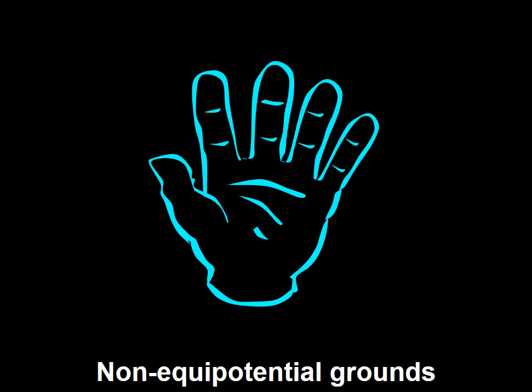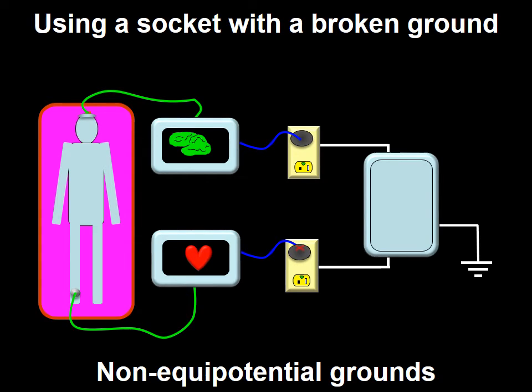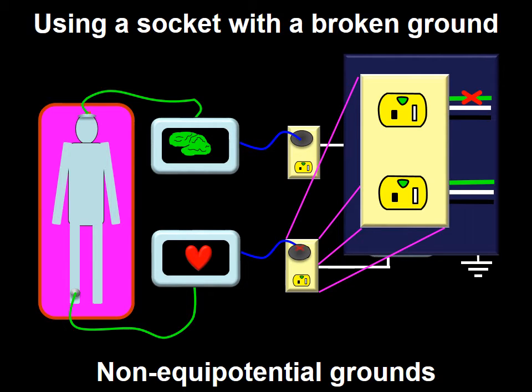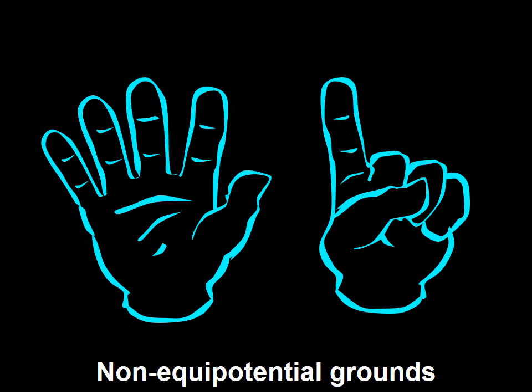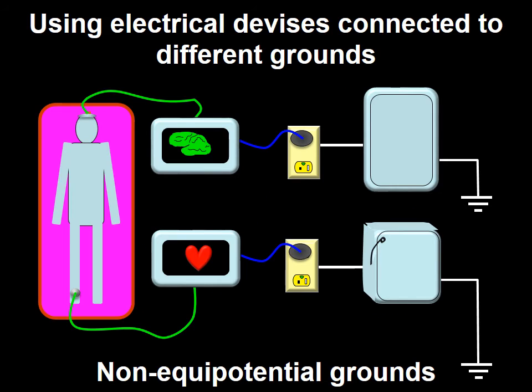The fifth situation is when the broken ground is behind the electrical receptacle — that is, between the wall receptacle and the electrical box. The consequence is a potential voltage imbalance. The sixth and final situation is when two equipments connected to a patient are ultimately coupled to different electrical boxes, and the boxes are linked to ground through lines of unequal distance. In this situation the one with the longer line will have more resistance, and if exposed to similar current will generate higher voltage, thus creating a voltage imbalance.